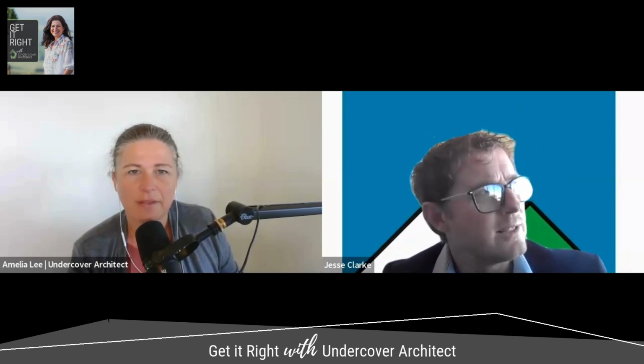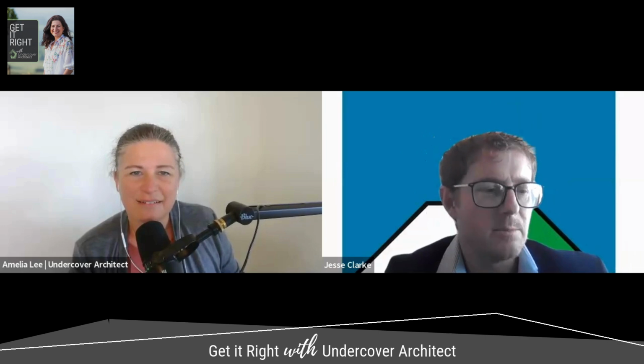So it all, like I said in the intro, stems back to energy efficiency. We start to change the dynamics of a building when the government pulls a massive lever and says you must insulate your building and keep insulating more and more every few years. Actually, they haven't really cranked it much for the last 10 years, but it did increase from nothing to a decent amount of insulation. Then you change the dynamics of the building. You're retaining heat in the building, or blocking the heat out of the building. But when you change the dynamics of that building envelope, if one side is going to stay warmer, the other side is going to get colder because you're retaining that energy. So the cold surface then becomes a potential risk of high humidity, condensation, mold growth.